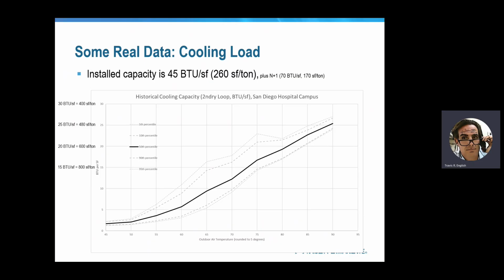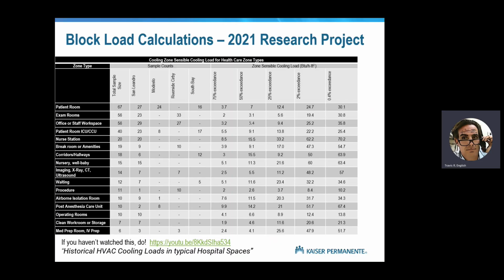So what's going on with this oversizing thing, right? It's almost a cliche, by the way, to say that HVAC engineers oversize the cooling by double. What's actually going on with that? So again, let's look at the data. This is a nice big data project that we did last year. We literally went into every zone in one building and looked at the historical cooling load in every hour of the year. We actually started off with one building and then we ended up adding 3 more buildings. So it's a lot of data.